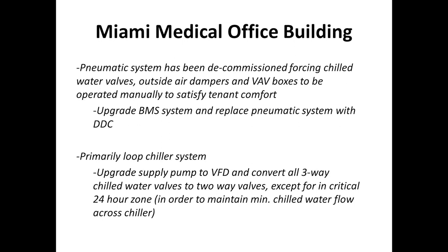Our recommendation was to upgrade the BMS system to accommodate DDC controls, and then also put in electronic actuated valves at each of those points to allow them to have control over the system and modulate the system based on building loads and cooling loads, based on outside air temperature and inside air temperature conditions.